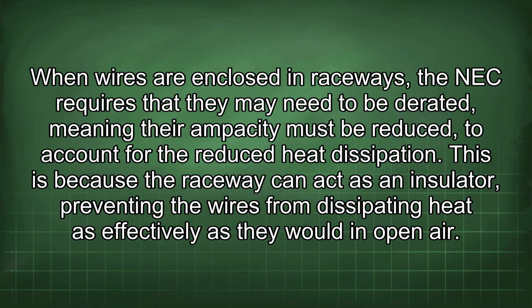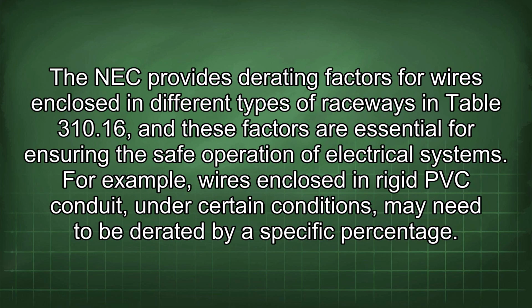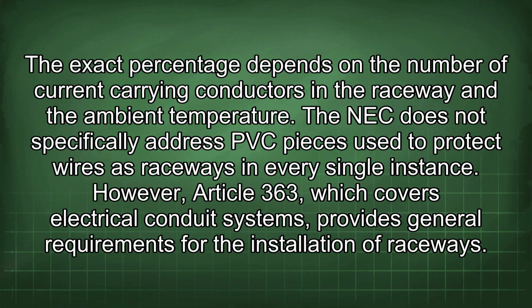This is because the raceway can act as an insulator, preventing the wires from dissipating heat as effectively as they would in open air. The NEC provides derating factors for wires enclosed in different types of raceways in Table 310.16, and these factors are essential for ensuring the safe operation of electrical systems. For example, wires enclosed in rigid PVC conduit under certain conditions may need to be derated by a specific percentage. The exact percentage depends on the number of current-carrying conductors in the raceway and the ambient temperature.